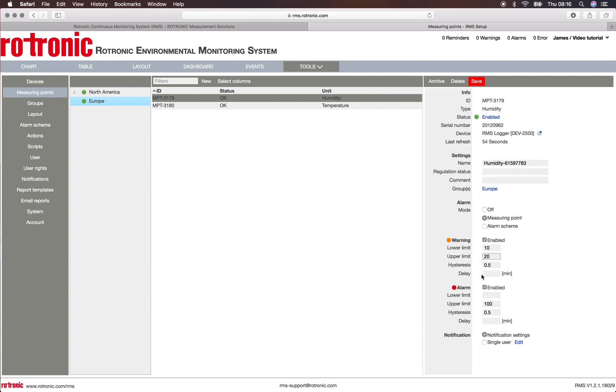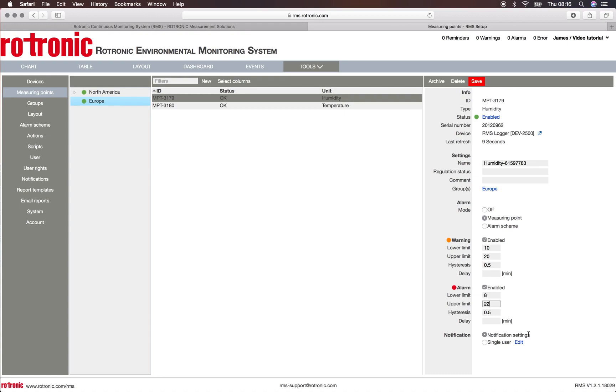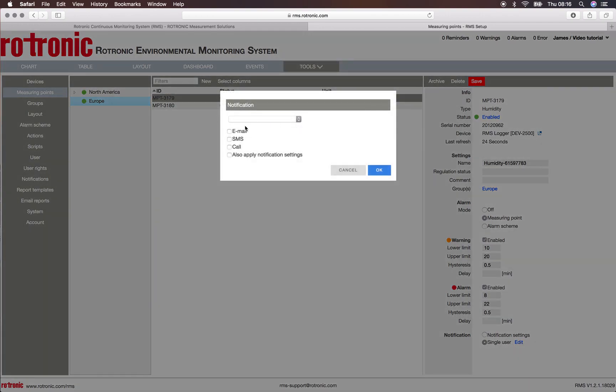I can set as well a hysteresis and a delay, and on the alarm level I will set the alarm at 8% relative humidity and 22% relative humidity. Then I can choose either notification settings—please see the RMS video about notification settings to understand this function—or I can choose a single user by clicking on single user edit, and I can choose here either James or Mike Brown.